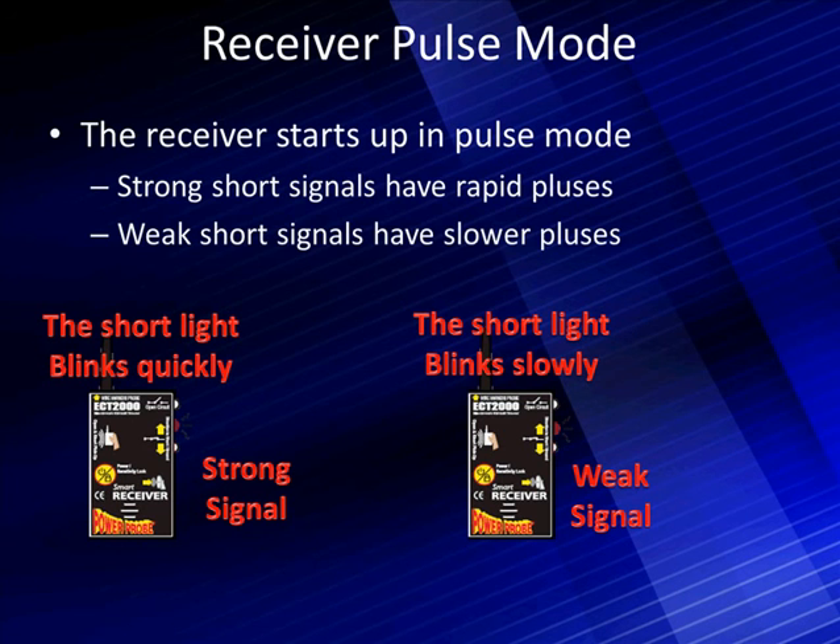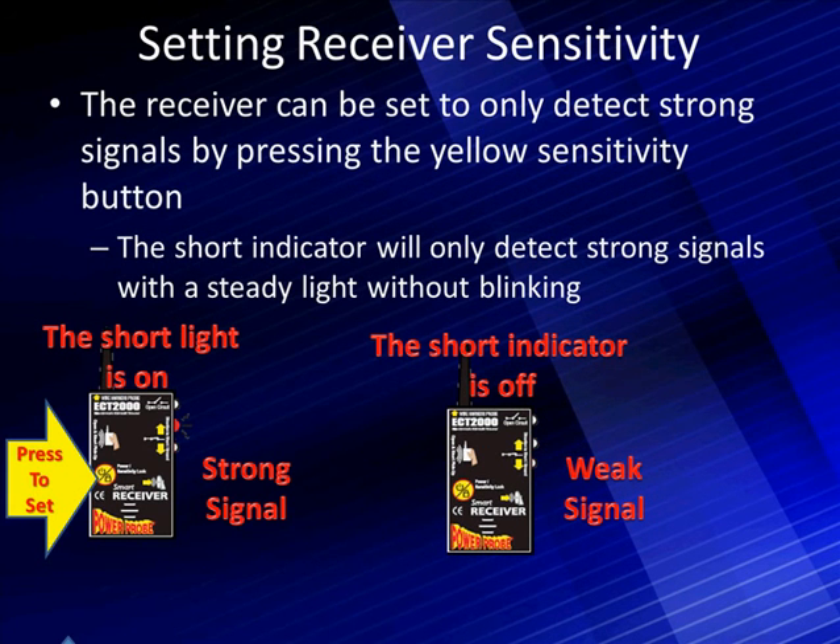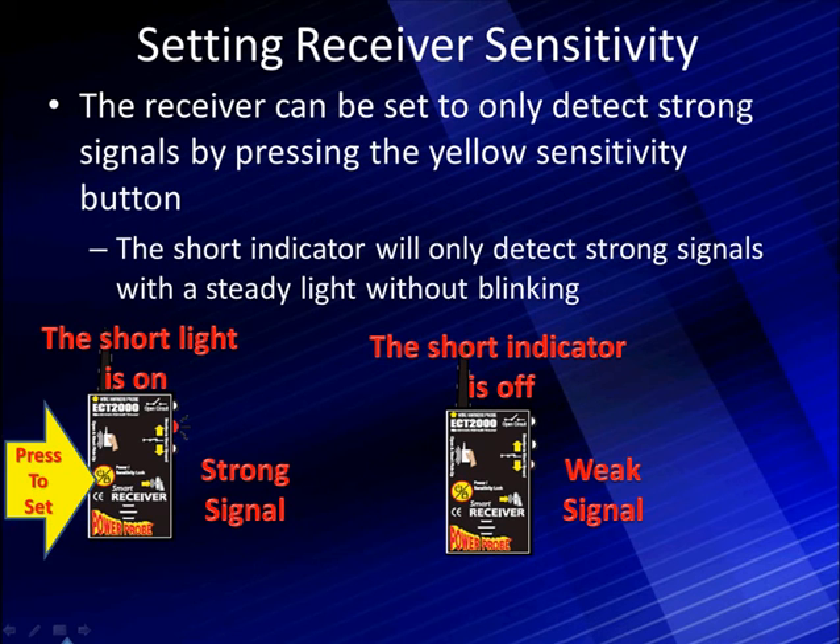One thing we can do to make our life easier is set the receiver to detect only strong signals. We do that by pressing the yellow button that says 'press to set' while the strong signal light is on. When we then move it to a weak signal, the lamp does not light because it's already set for low sensitivity. This means bulbs we didn't remove would not show us a false signal, and parallel circuits with current going in two directions will also register as a very weak signal.